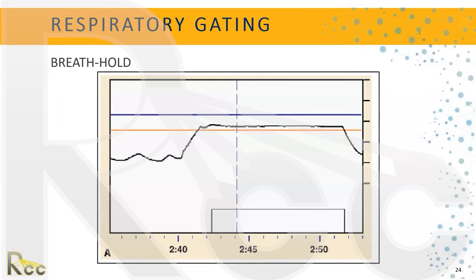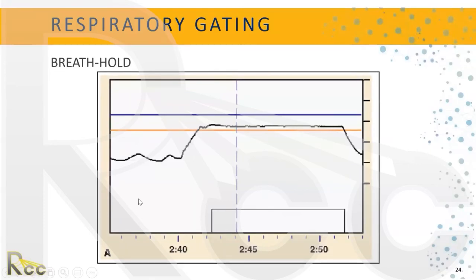With the breath hold, the software shows the patient taking in a breath and holding it. As long as they're within the threshold we've set, the beam will be on. For breast treatment, someone can hold their breath that long. But for a very advanced IMRT lung treatment, breath hold may not be feasible for the full duration. That's why patient education and training is so important — they need to know what's expected of them.